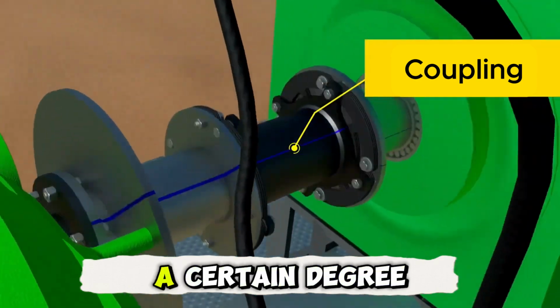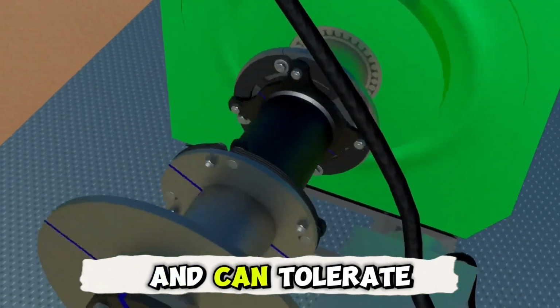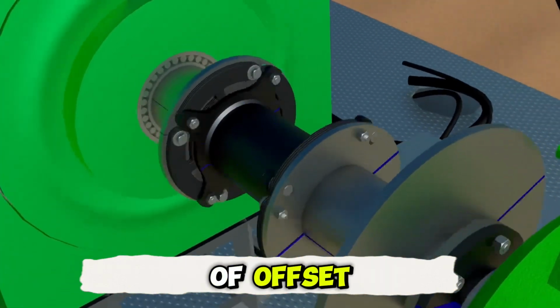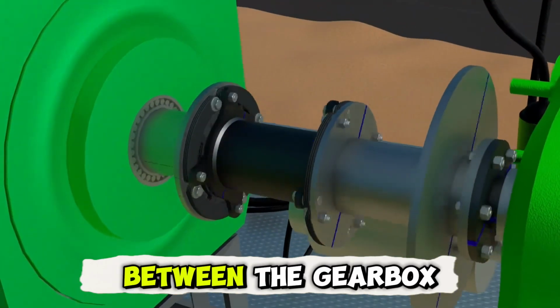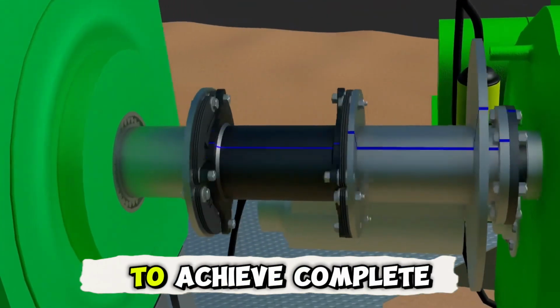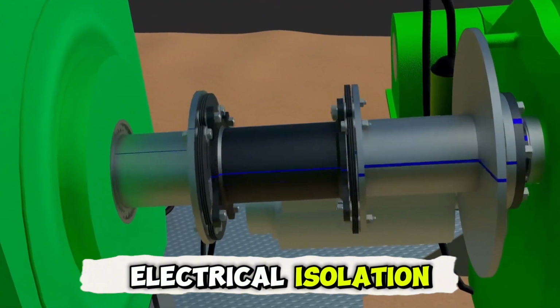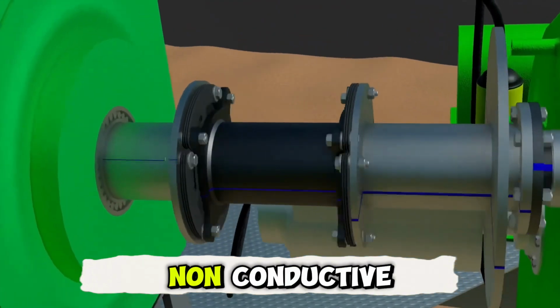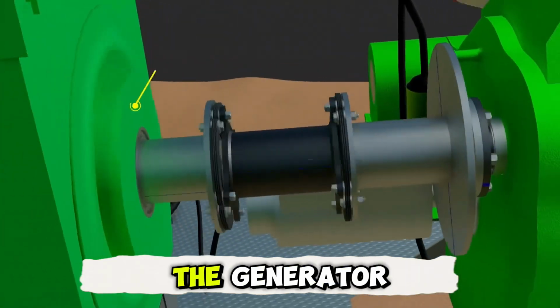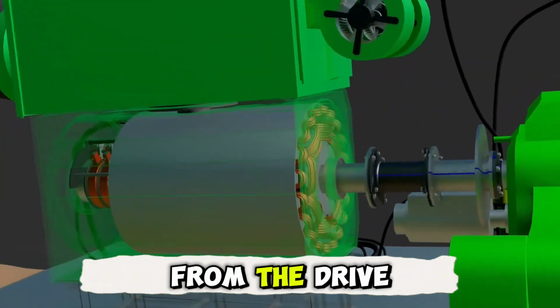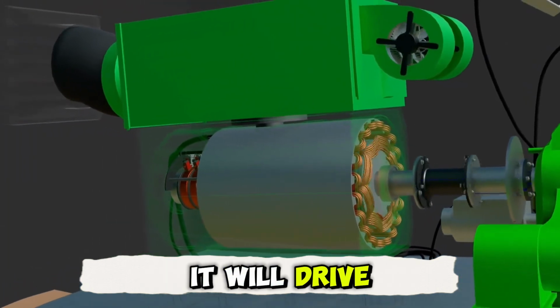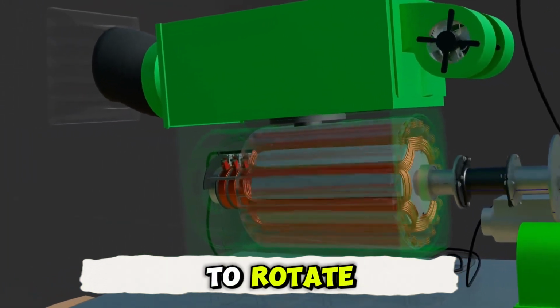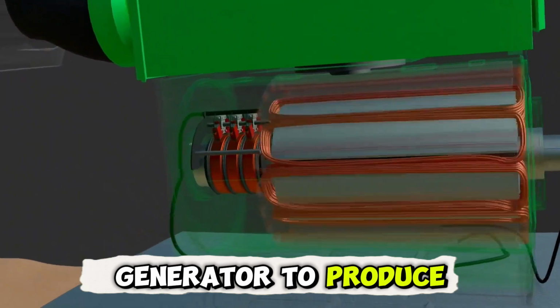The coupling has a certain degree of flexibility and can tolerate a certain amount of offset. This connection method allows the gearbox and the generator to achieve complete electrical isolation, because the coupling is made of non-conductive composite material. Next, the one at the back is the generator. Once the power from the drive shaft comes over, it will drive the generator's rotor to rotate, thereby driving the generator to produce electricity.